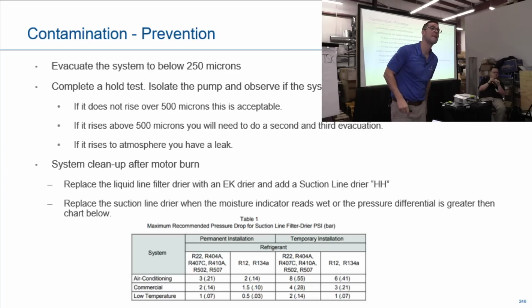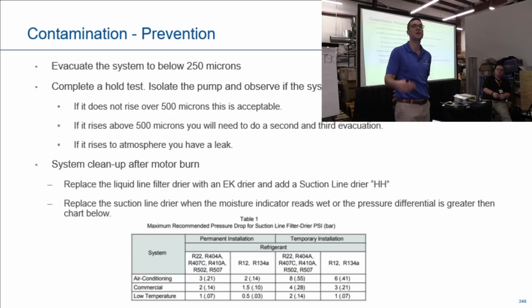You're talking about vacuum. What do you recommend you get the vacuum down to on a compressor? Well, it's all about the vac pump. If you can pull it down to between 250 and 500. I've been pulling them down to under 200. Okay. That shouldn't be an issue.